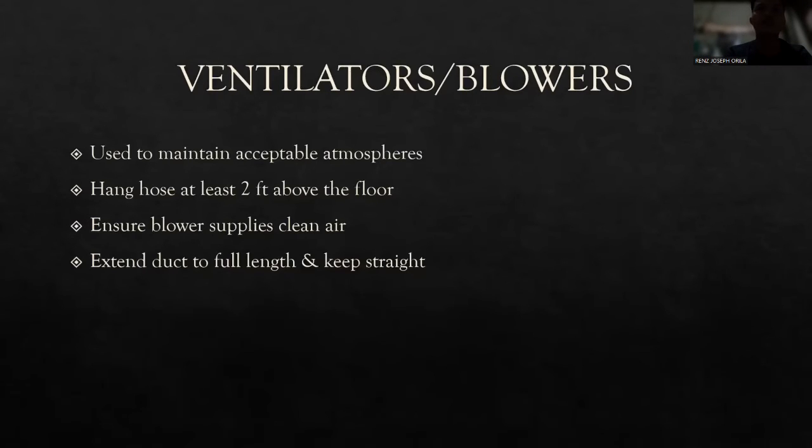Ventilators or blowers. It is used to maintain acceptable atmospheres. Hang hose at least 2 feet above the floor and ensure blower supplies clean air. Extend duct to full length and keep straight.